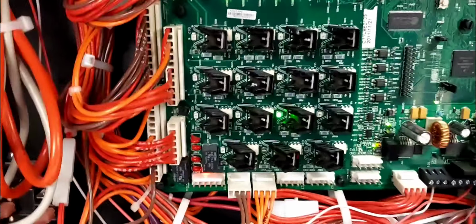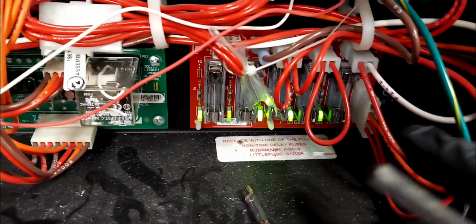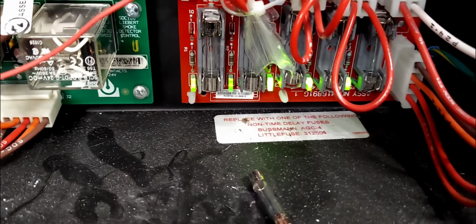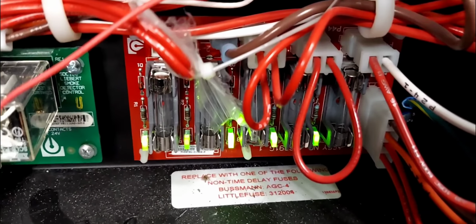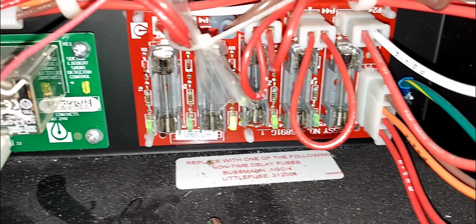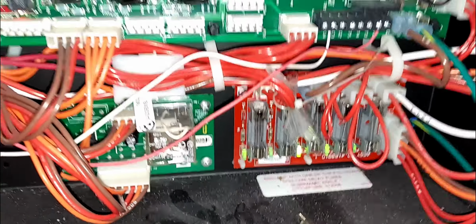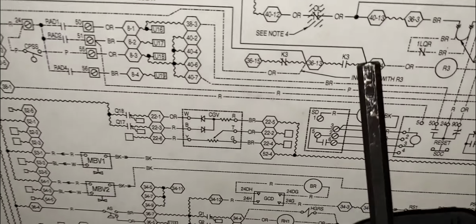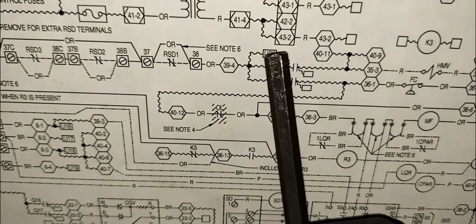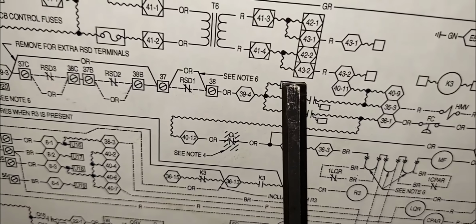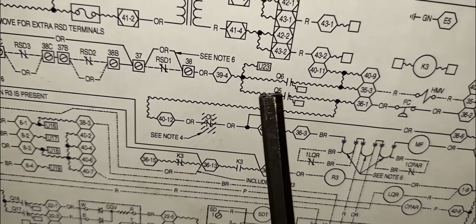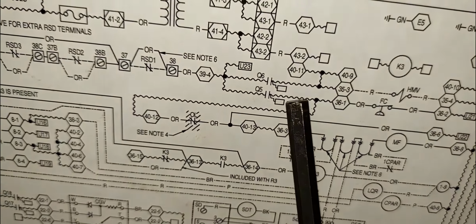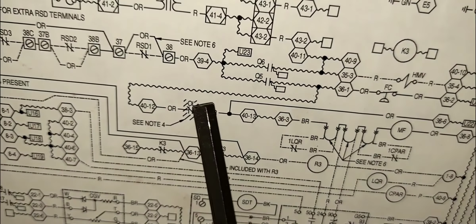All right, so our main fuse is good, and this is where the main fuses are. And I could see all of them are lit up. Those green lights on the fuses, they're all on. So all my fuses are good. So we verified that we're getting 24 volts on U23 because that input is lit up. So that means 24 volts is passing through my triac, which is currently on. So we got this bit right here.